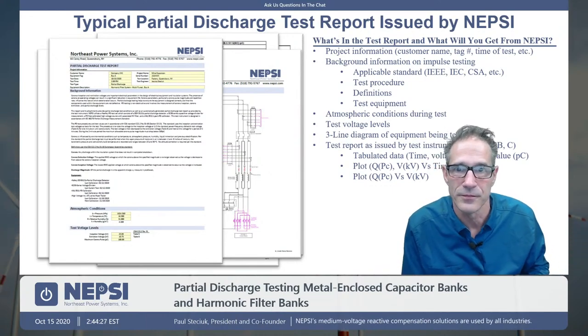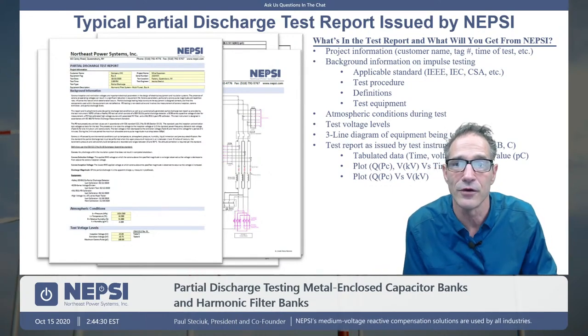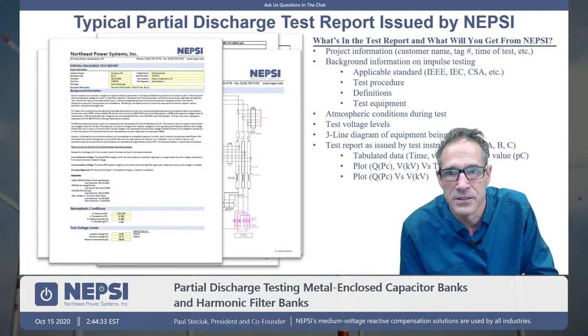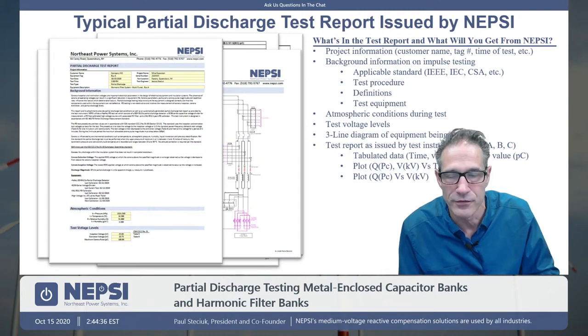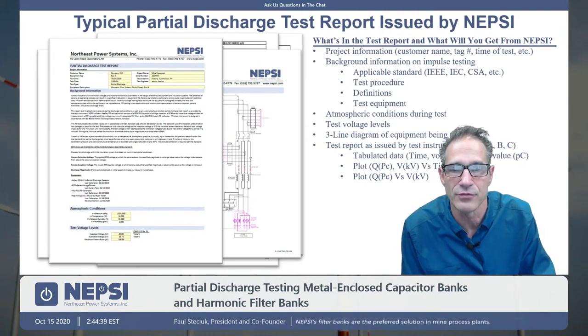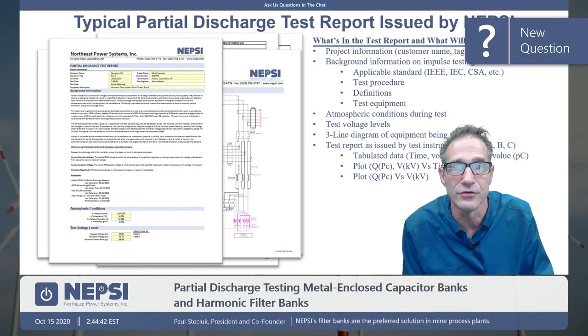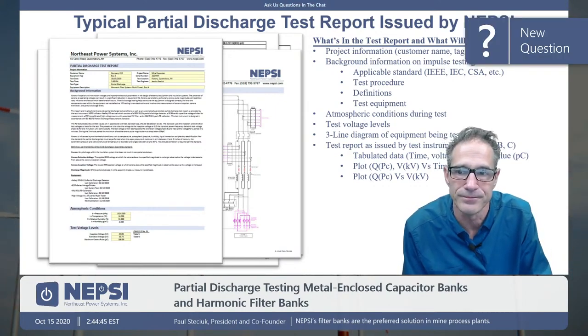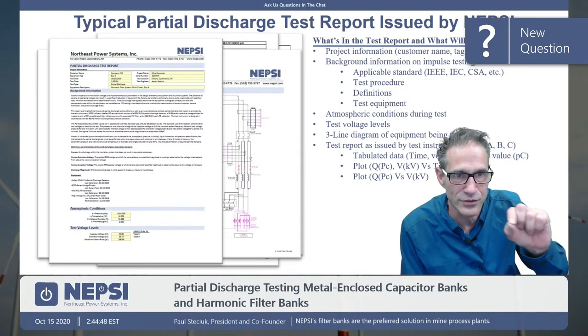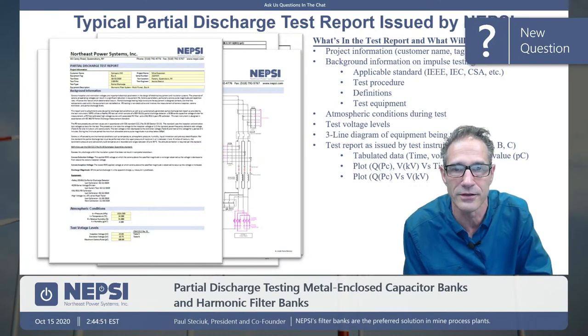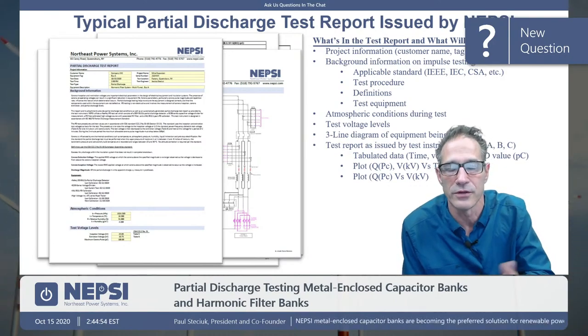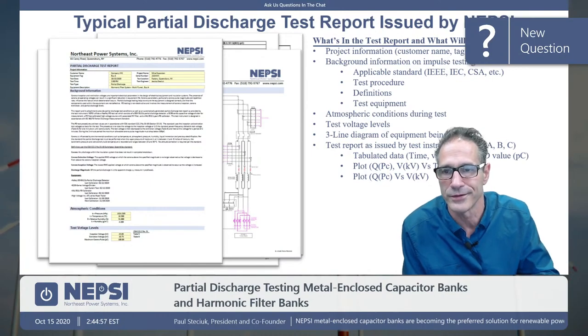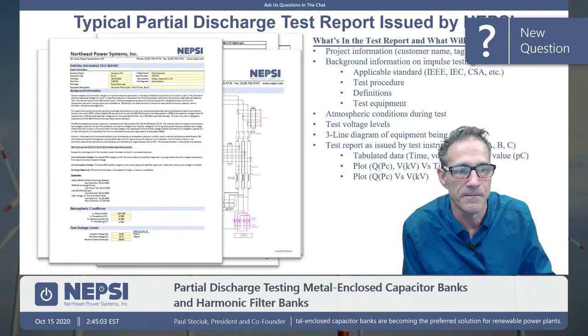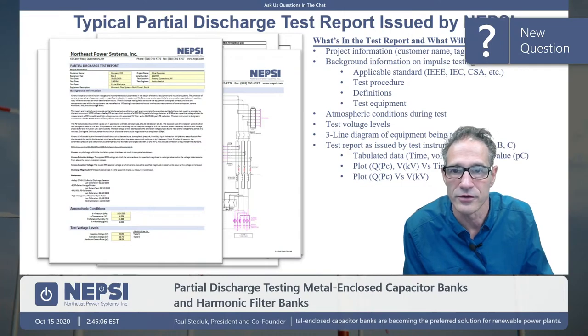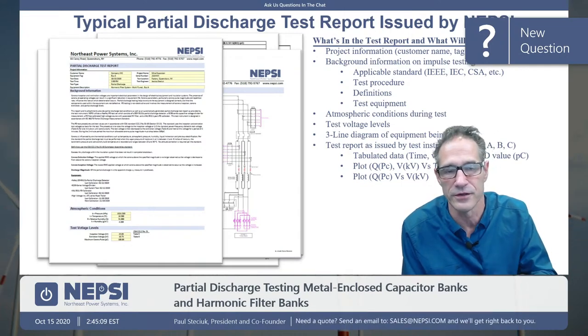Okay, test reports. Just like the SFRA and the impulse test, you have to generate a report afterward, and it's what we hand our customers. So we have a partial discharge test report. Incidentally, that Haefely Trench instrument does a lot of the analysis to determine the partial discharge level, so there's a lot of detail in that instrument. But this instrument creates the test report. We put the conditions in there, the equipment, the environmental conditions, and come up with the voltage levels and the test standards, and then we create a test report that we hand to our customers. And there are three, phase A, phase B, phase C, that we're doing.